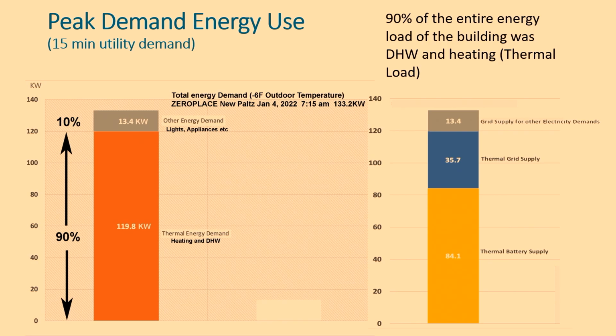However, here comes the trick: this was not all coming from the grid. Of the 84 kW, 63% came from the ground, and it shaved off what the grid was using. So the actual grid draw for thermal heat was 35 kW, and 13 kW for everything else - elevators, plugs, lights, stoves, dryers.